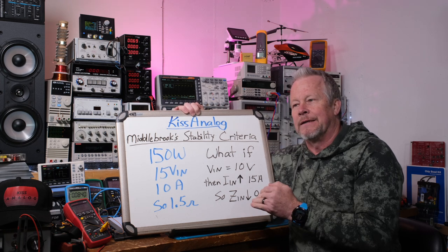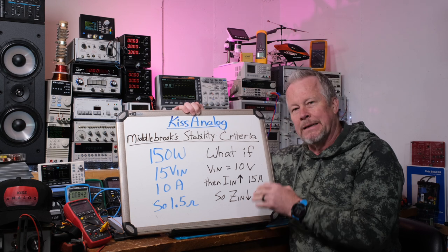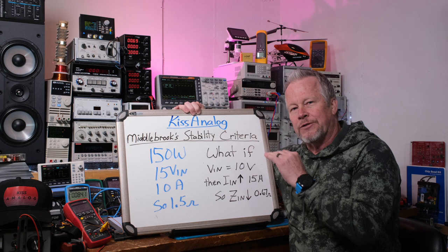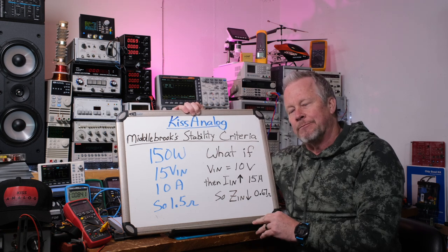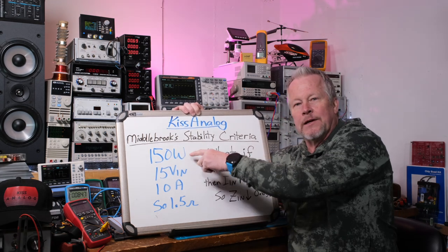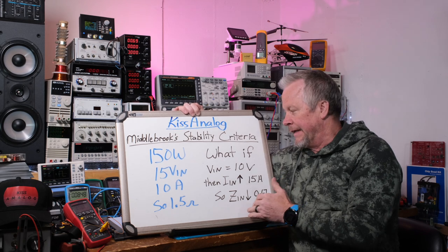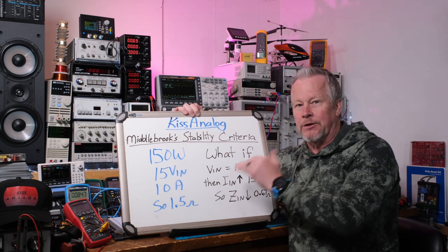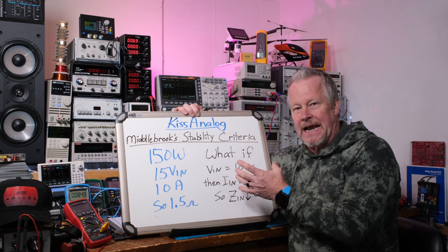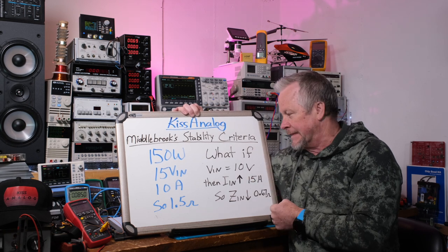A linear power supply doesn't behave this way — as the voltage drops, at a certain point the output voltage starts to drop out. But a switching power supply not only tries to maintain a constant voltage on the output, it tries to maintain constant power. If it needs 150 watts to maintain that output, when the input voltage drops it's still going to try to draw 150 watts — meaning the impedance has to drop. The power supply is saying 'give me more current.' That's your negative resistance.